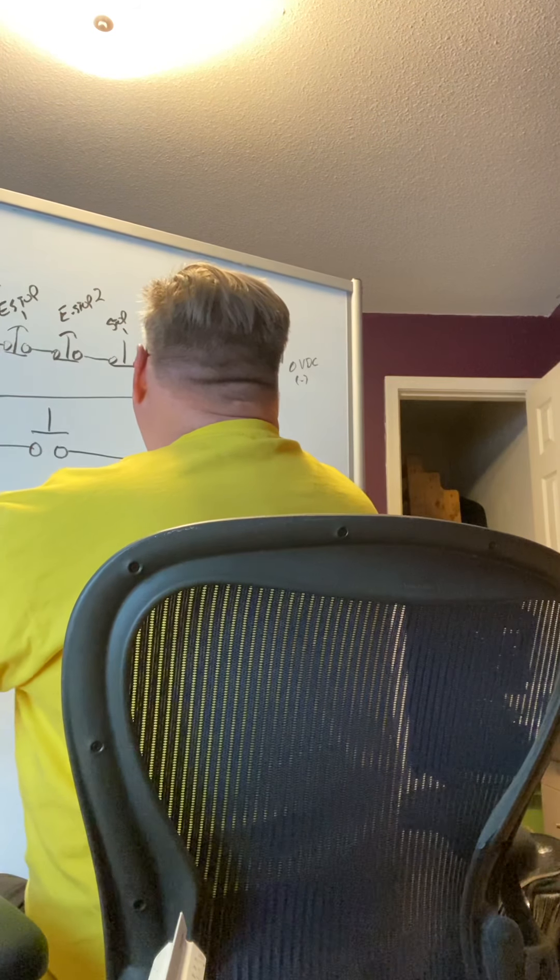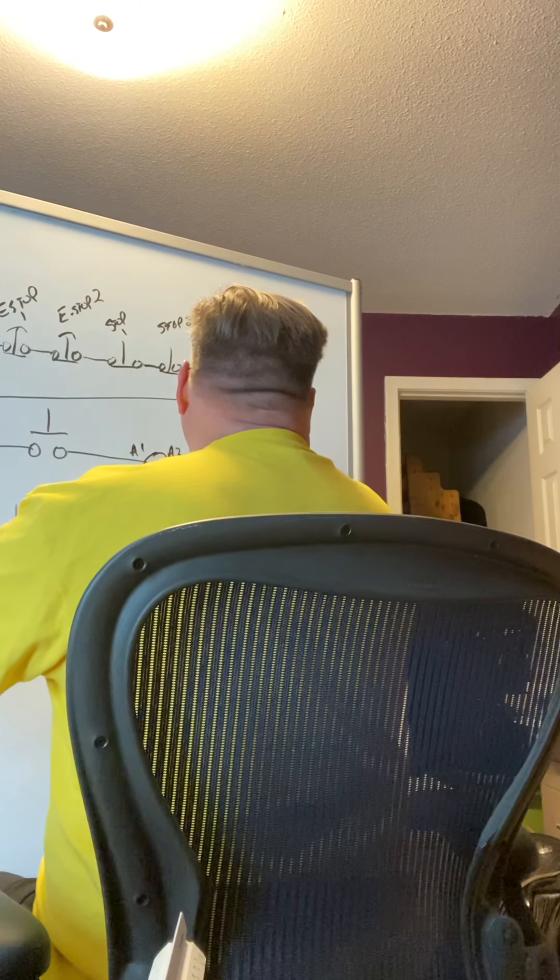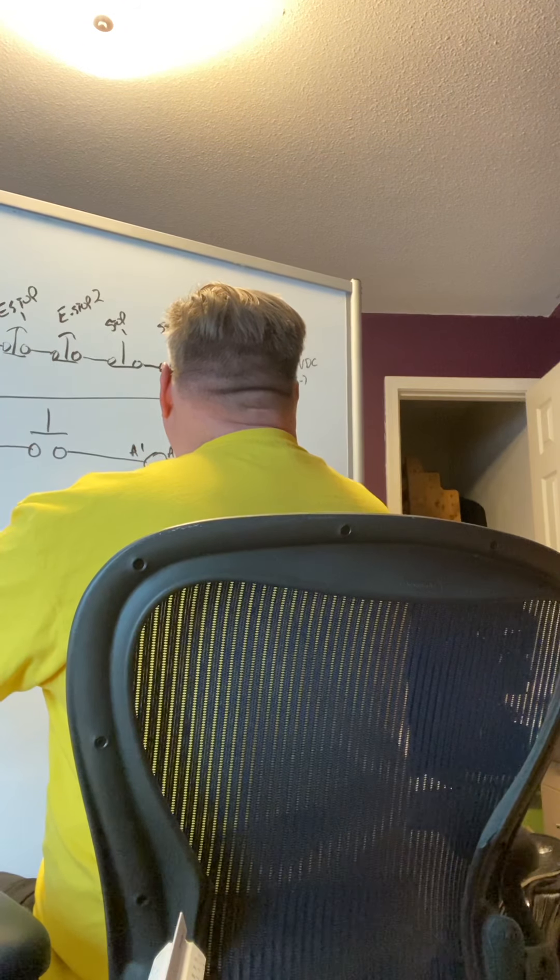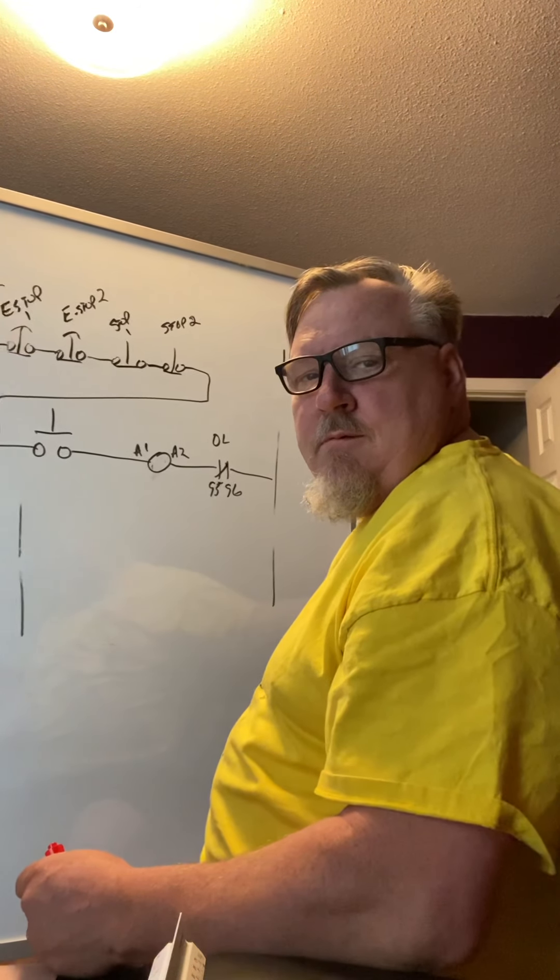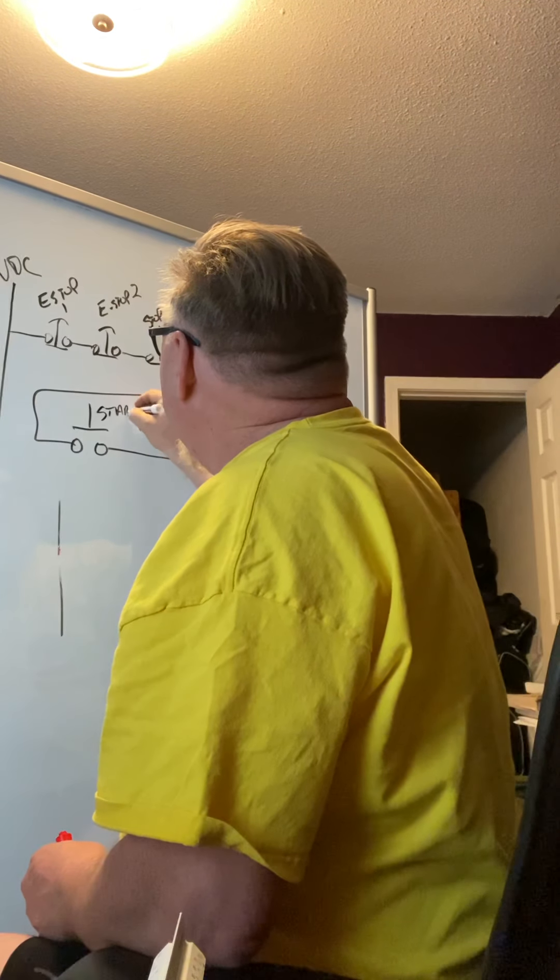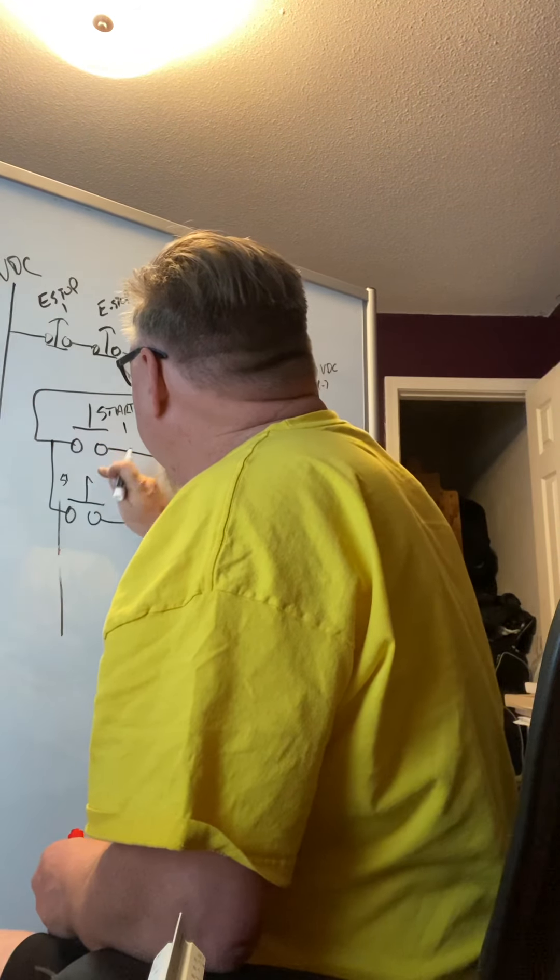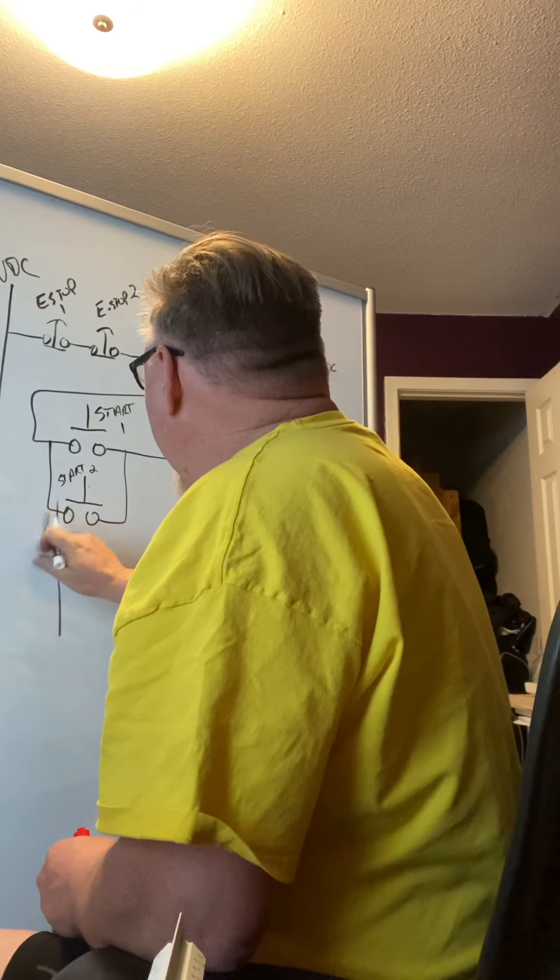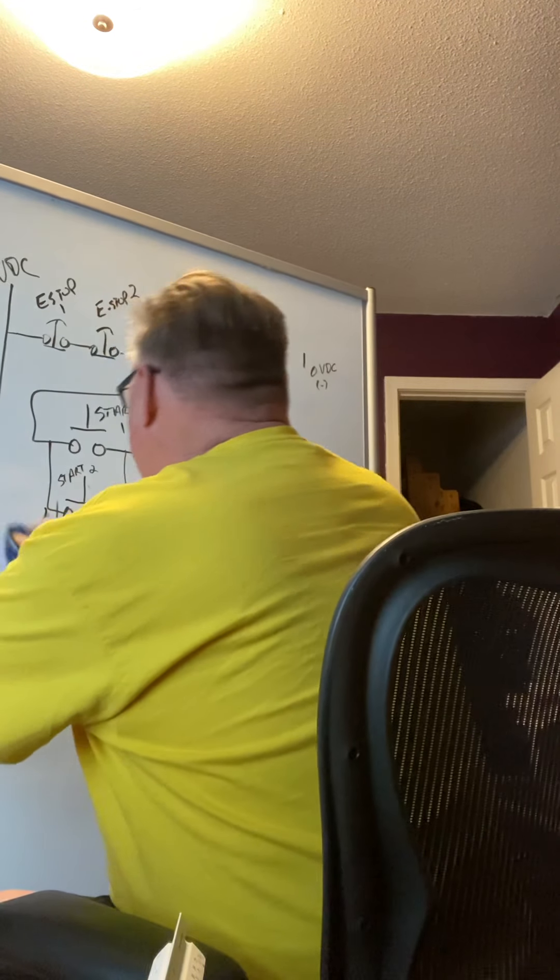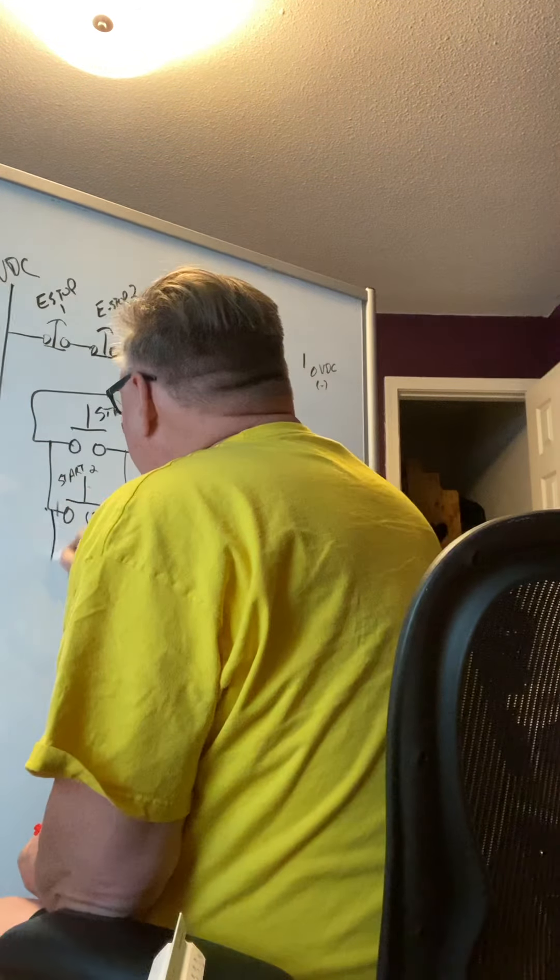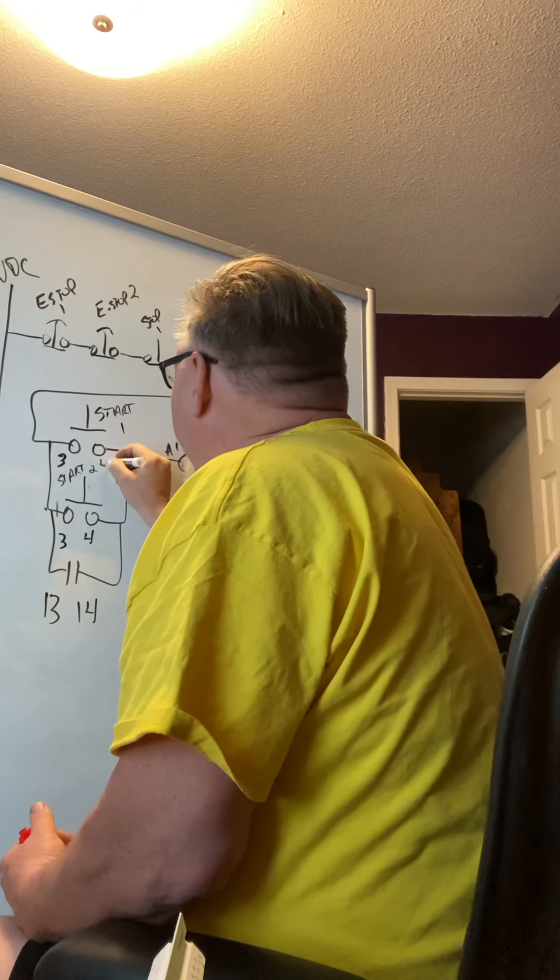So I'm going to bring this back round here. So we have a start here. We have our armature, A1, A2 here, our normally closed overload, 95, 96. If we've got, these are stops. All our stops are in series. But our starts, we still have our latch. So 13, 14, 3, 4, 3, 4.